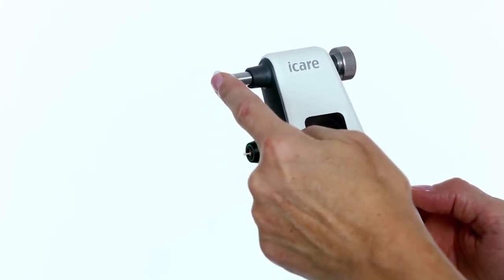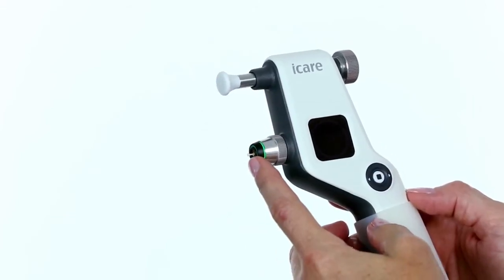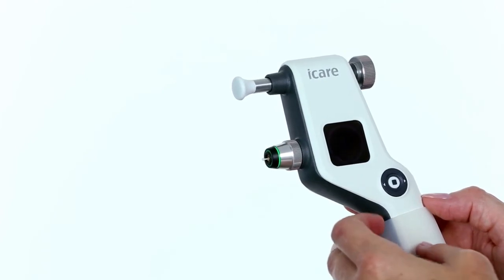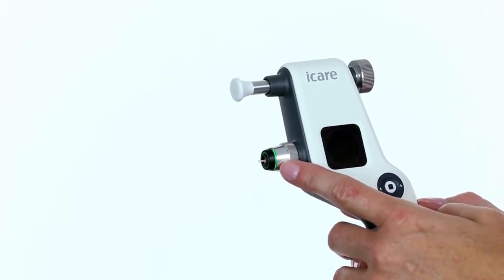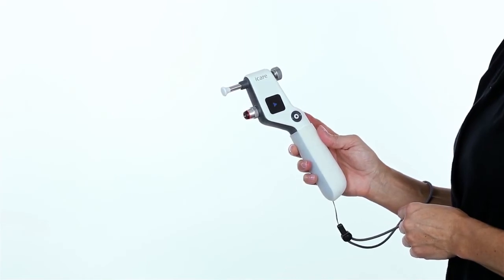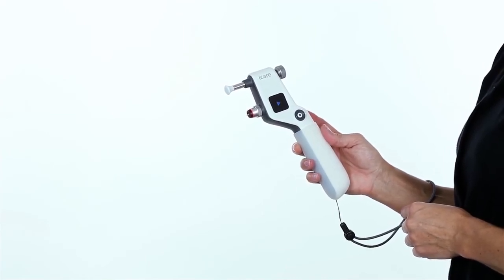Place the forehead support on the patient's forehead. Aim the probe in the center of the eye and the distance of the probe to the cornea should be four to eight millimeters. The green probe base light indicates proper alignment. If the probe base light is red, the alignment is incorrect.